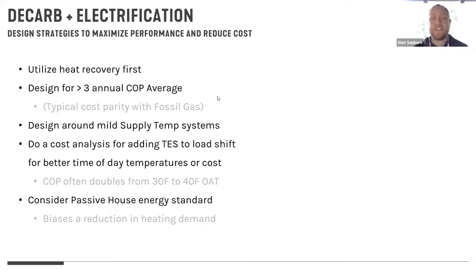I definitely encourage every project to do a cost analysis around thermal energy storage. You guys have more stable demand charges than we do out here. But for us, TES, or thermal energy storage, is a huge asset to be able to shift our loads from one time of day to another. And more so, it gives our clients flexibility and reduces their long-term risk to utility demand charge changes. If I can design in a certain amount of thermal energy storage today, which say gives me 6 to 8 hours of load shift, that gives our client a tremendous amount of flexibility of when they deploy that. And so if demand charges in 5 years or 10 years change, we can change the algorithm, change when we shift that load, and they don't have to do anything else, they can still save money. So looking at that long-term value and risk avoidance for our clients is exceptionally important.